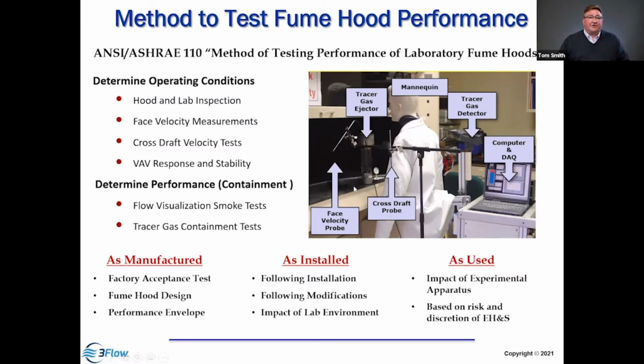Under that set of operating conditions, we're going to look at airflow visualization. What are the airflow patterns within the hood, and how well does it dilute and remove materials? And then subject it to the tracer gas containment test. Now these tests can be specified 3 ways. As manufactured, that's before you purchase the hood. You want to know everything you want to know about that hood and to design the system properly. So you test it, determine the performance envelope, and now you're ready to install it.